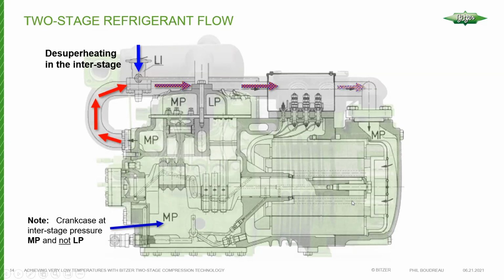So with that injection taking place, now we cool the refrigerant. So we do a little bit of pre-cooling before that refrigerant enters the motor, because we have to extract the heat from the motor to keep the motor happy. And then once the refrigerant passes through the motor, absorbing heat, it's going to enter the high stage cylinders, the final two in this case, for compression up to the final discharge pressure, and then it'll be off to the condenser, usually via an oil separator, being a very low temp system.